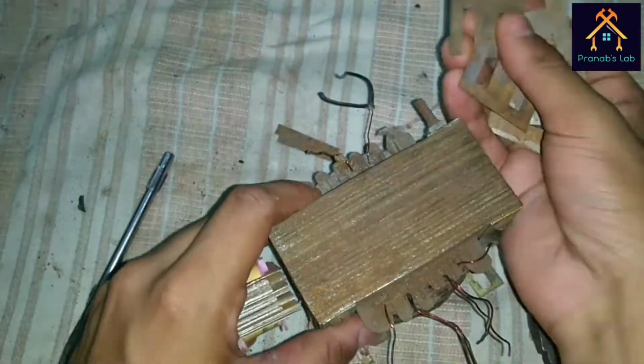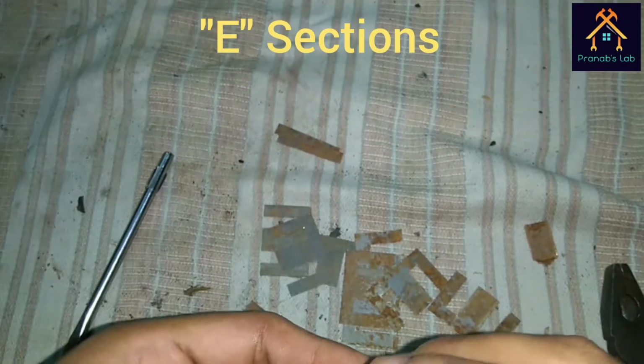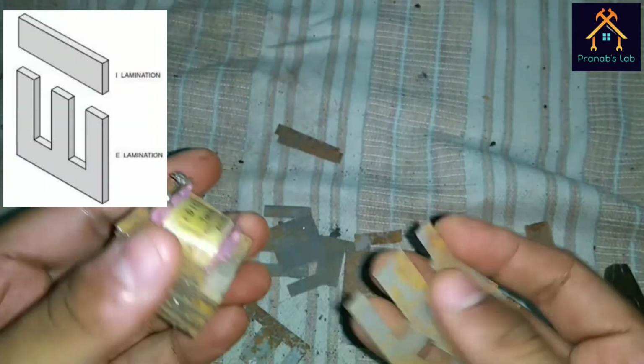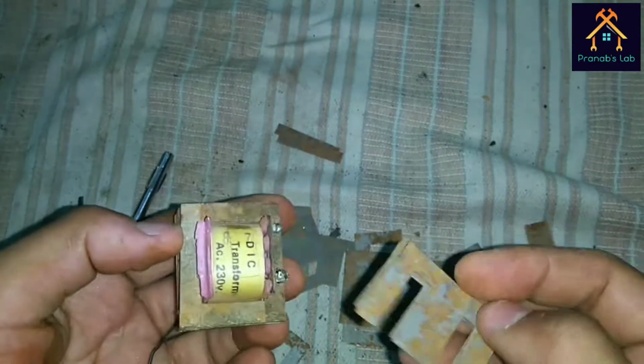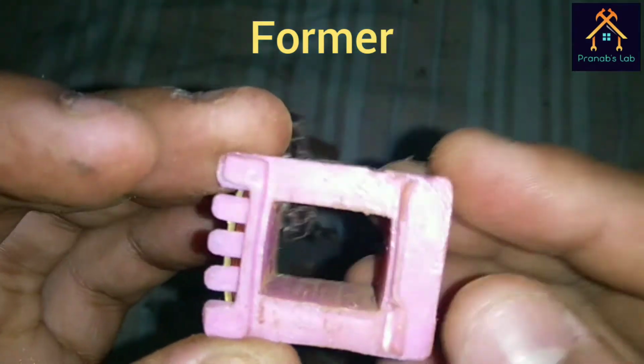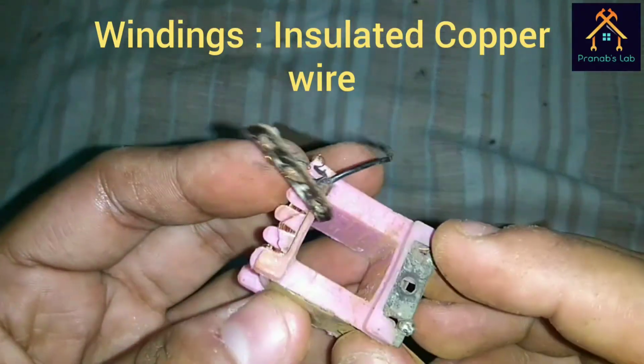These are the thin laminations of the E section, and these E sections are fitted in opposite directions with each other. You can see 3 to 4 E sections are placed together in the opposite direction. Now you can see the former of the transformer, and the windings are wound over the former, and this former is made of plastic, and these are the E sections.